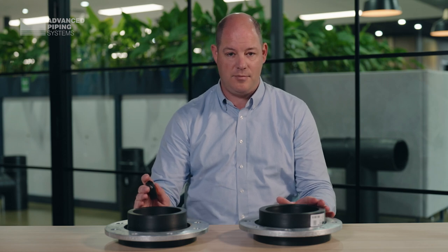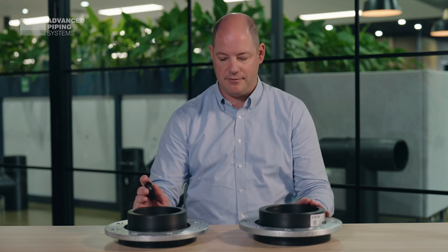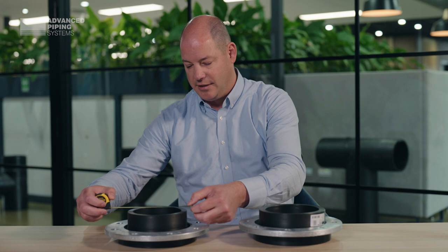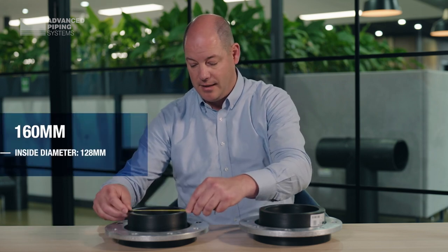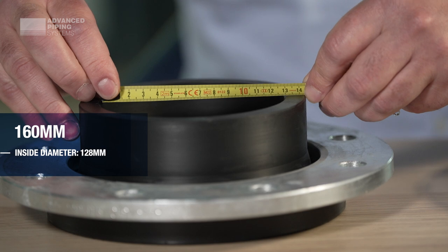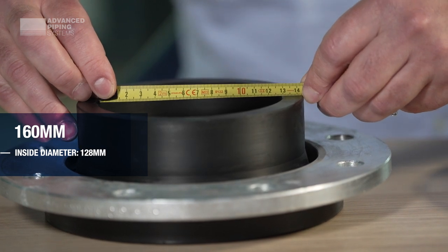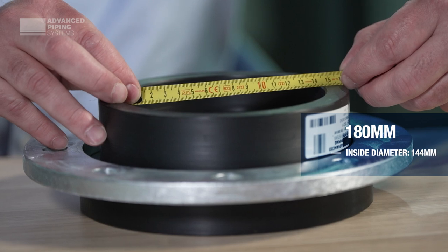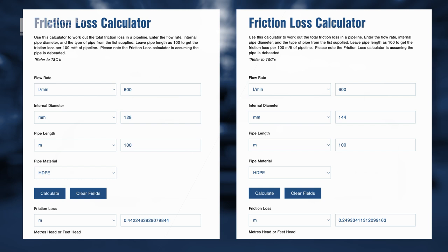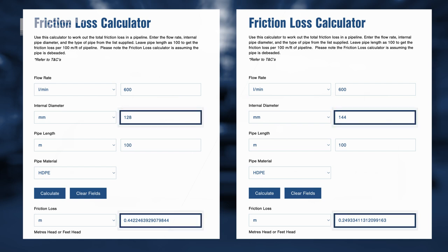The efficiencies that can be gained from upsizing your six-inch piping to 180mm is massive. Firstly, the outside diameter is 160mm and the inside diameter of 160mm is 128mm. The inside diameter of 180mm is 144mm. That's an approximately 13% increase in inside diameter. The efficiencies that can be gained through this upsizing of internal diameter is massive.